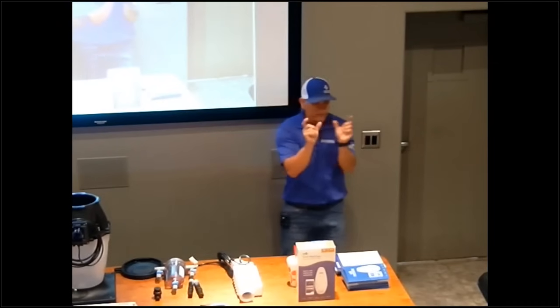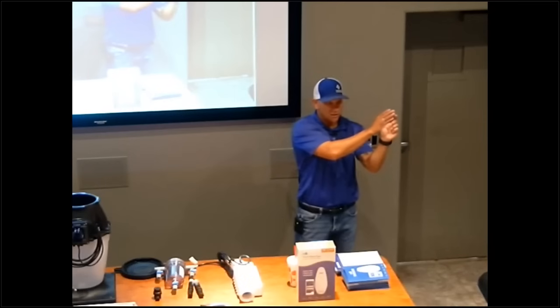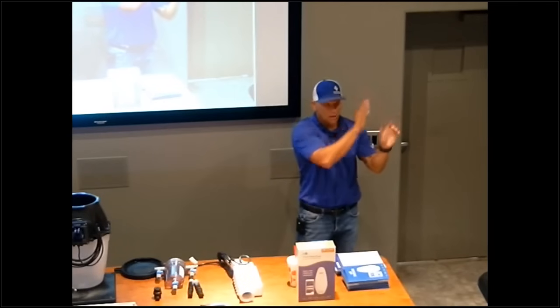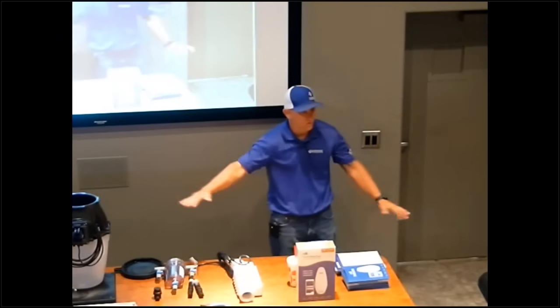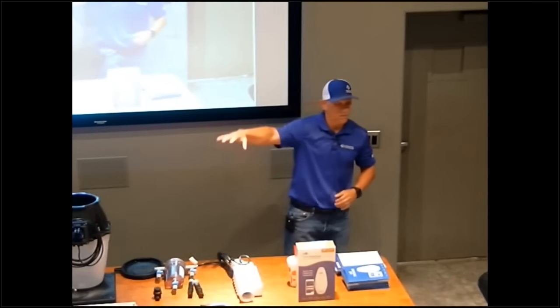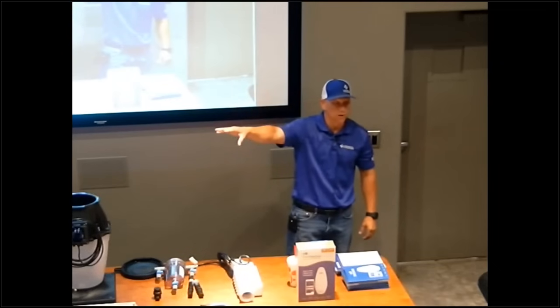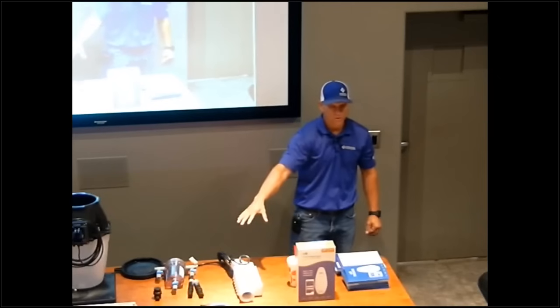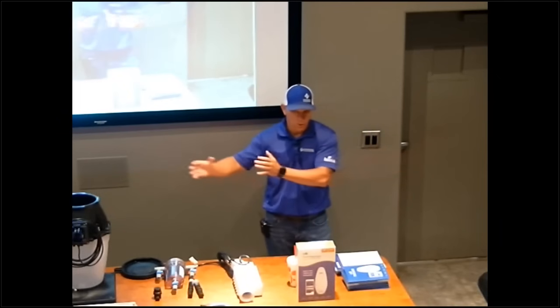If you split it, the low speed kicks on, and as soon as the low speed's done, everything's off — all the equipment's off. Then your high speed comes on by itself, just the pump, not the equipment. You want the equipment to run during both low and high speed.